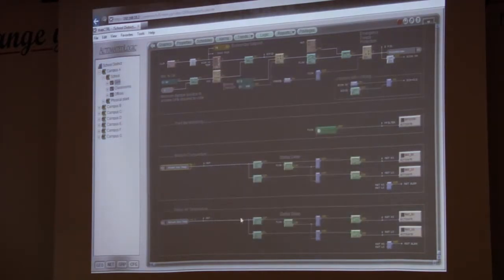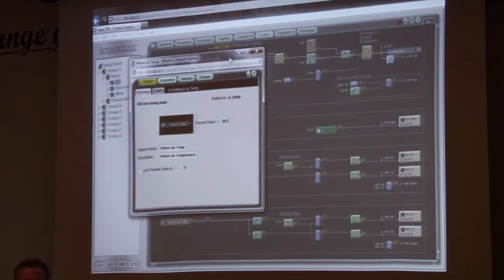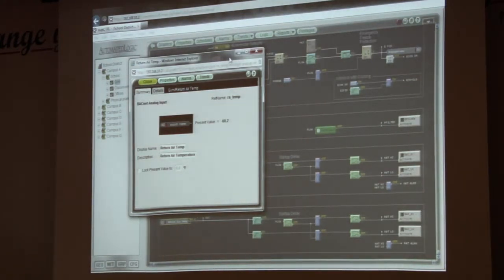So we've locked one of them. Let's make sure that we can do it again. Let's go ahead and do the other one, which is the return air temp, which will be your chill water supply, your chill water return temperature on there. And we want to make sure it has to be a different value. We don't want to look at a trend and they're sitting on top of each other. So go ahead and lock it at 77. How's that sound? All right, we're going to lock it at 77.